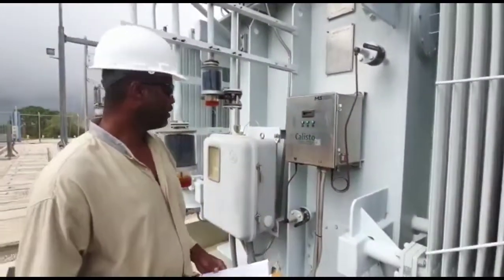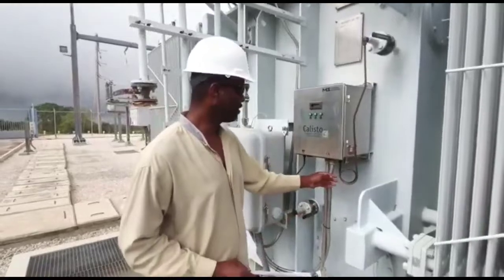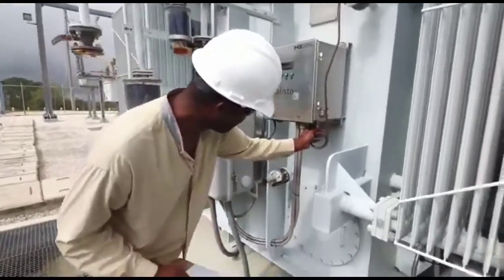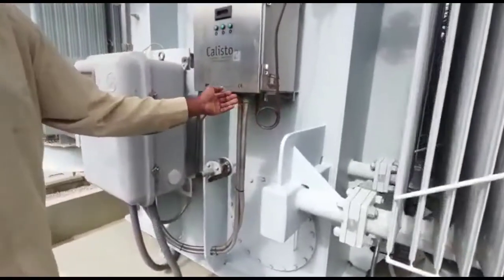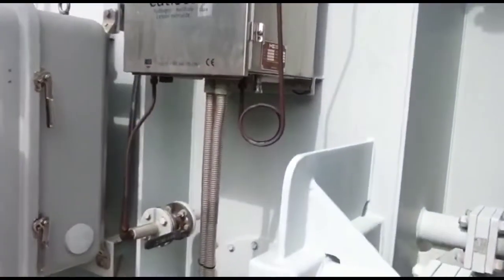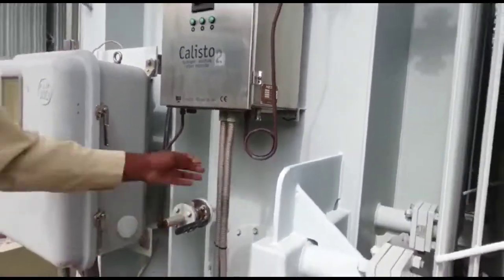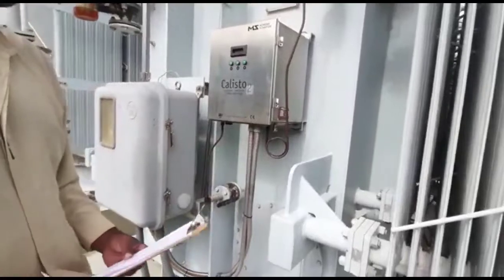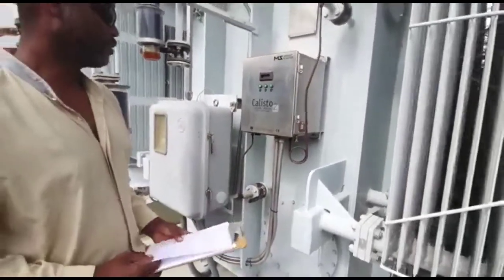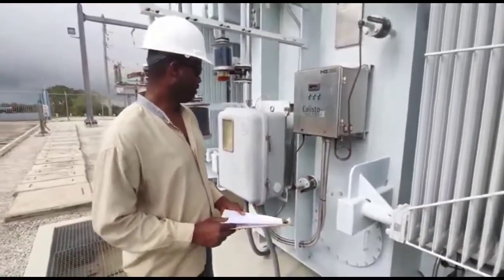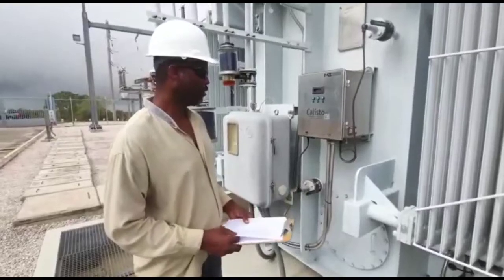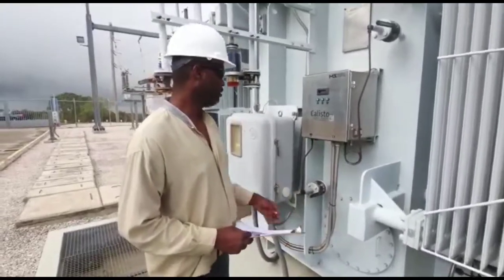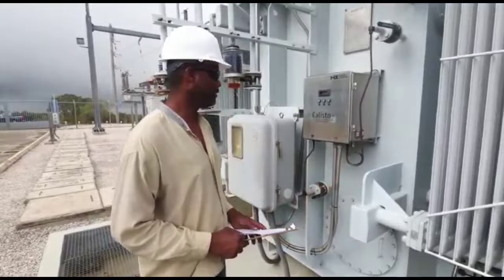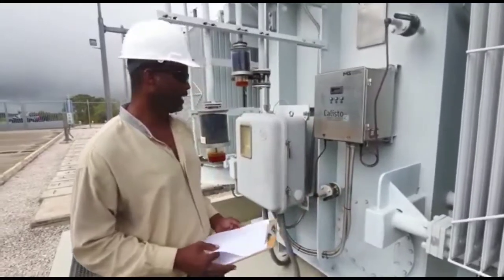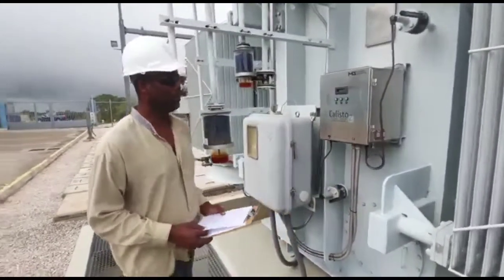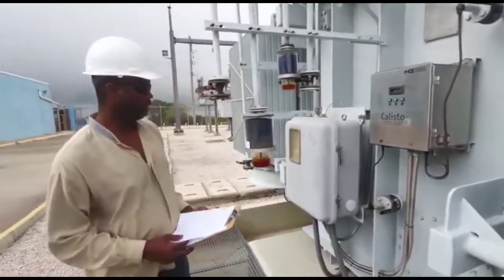You also have an oil sampling port right here that you will use when you're taking an oil sample from the transformer. You have to take an oil sample from the transformer every 6 months to make sure it is working correctly. Just like how you would go to the doctor and do a blood test. You will take some oil from the transformer, send it to the lab, and they will test and let you know the transformer is working okay.